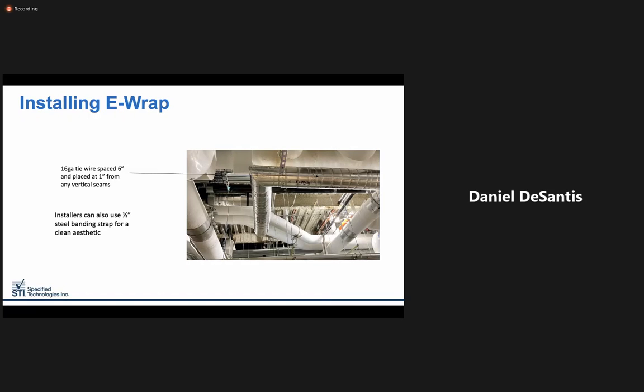Here is an image showing the finished installation on a fuel oil line. In this case, the contractor opted for the use of 16-gauge tie wire on the outermost layer, but 1/2-inch banding coil is also acceptable in this scenario. Regardless of which method is used, banding coil is always only required on the outermost layer.